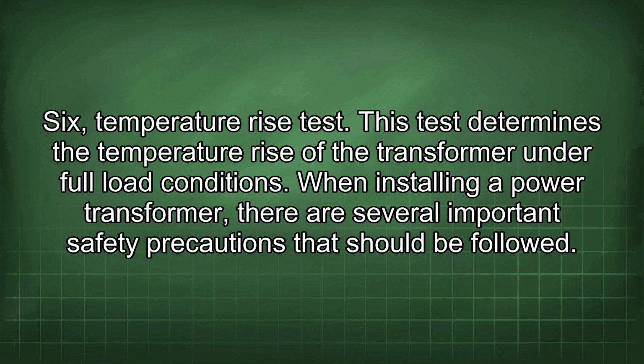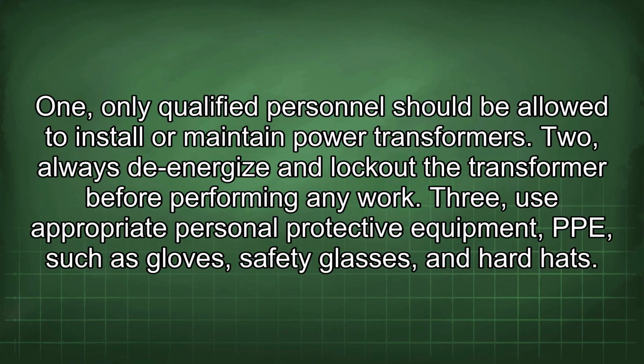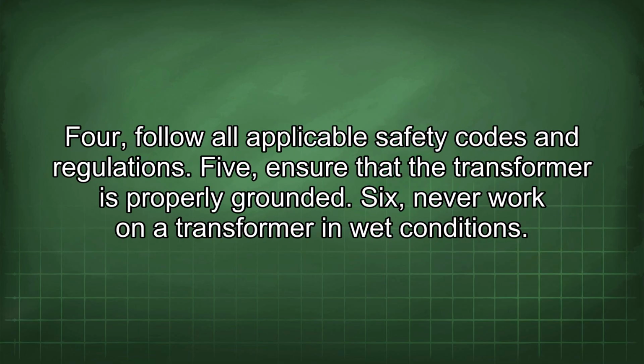When installing a power transformer, there are several important safety precautions that should be followed. 1. Only qualified personnel should be allowed to install or maintain power transformers. 2. Always de-energize and lock out the transformer before performing any work. 3. Use appropriate personal protective equipment, PPE, such as gloves, safety glasses, and hard hats. 4. Follow all applicable safety codes and regulations. 5. Ensure that the transformer is properly grounded. 6. Never work on a transformer in wet conditions.